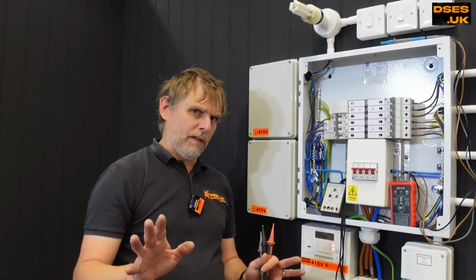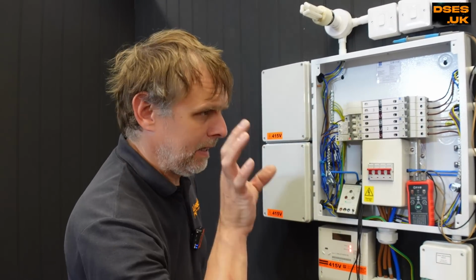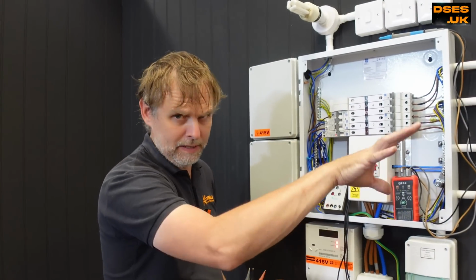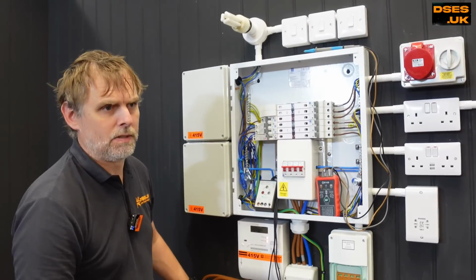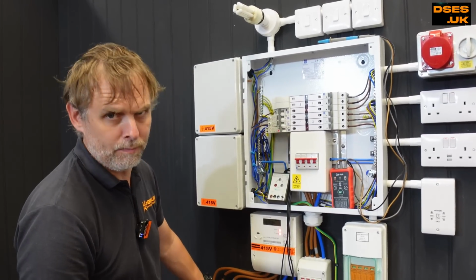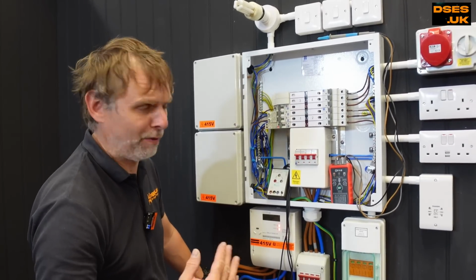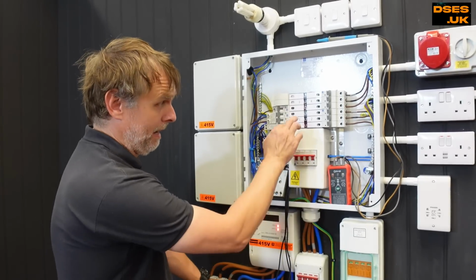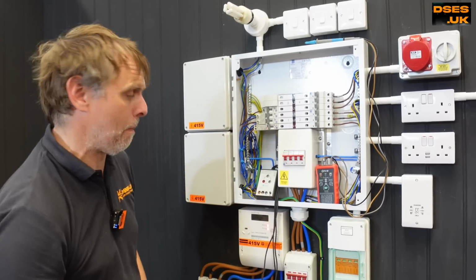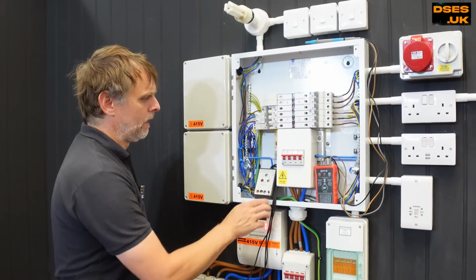Right, phase rotation? Phase rotation. Okay, phase rotation - we want to make sure that the commando socket thing back there, the TPN PE plug, is providing all 3 phases in the right order, i.e. L1, L2 and L3, brown, black and grey. And I've got 3 instruments to show doing that.